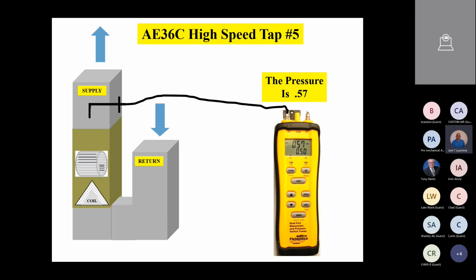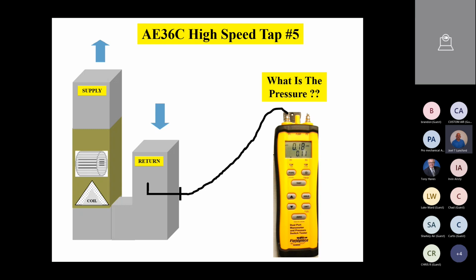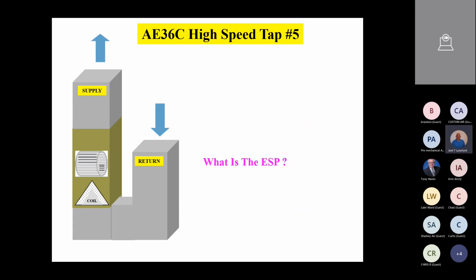So in this example, we have a 0.57 on the supply and a 0.18 on the return. So we can see right now that the majority of static pressure on this job is going to be on the supply side. Our external static pressure, or ESP, is 0.57 plus 0.18, which is 0.75. So taking a look at your AE36C airflow chart, we're on the high speed tap. We've got 0.75 inches of static. And so that's very high static pressure.